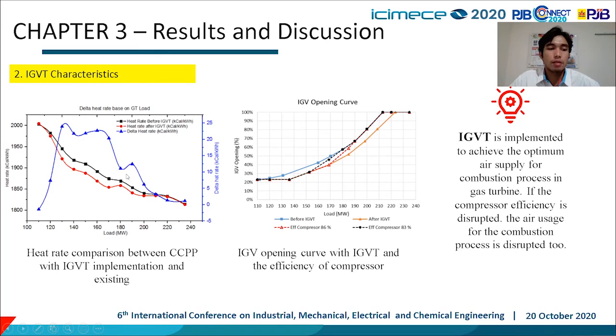210 megawatts. In this figure, it shows that the IGVT optimum area will be reduced if the efficiency of compressors decreases. This occurs when the compressor efficiency decreases because of low air compressed. Therefore, to supply enough air to the combustion process, the IGV position is set back to the initial position. The decrease of compressor efficiency firstly affects the IGVT in the high loads.